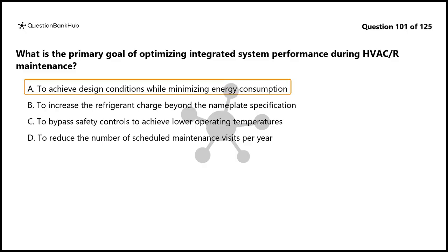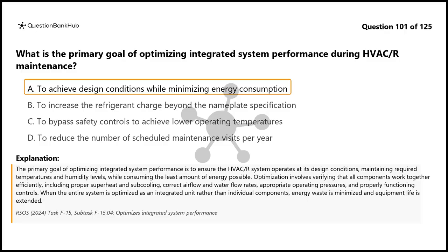The correct answer is A. The primary goal of optimizing integrated system performance is to ensure the HVAC/R system operates at its design conditions, maintaining required temperatures and humidity levels, while consuming the least amount of energy possible. Optimization involves verifying that all components work together efficiently, including proper superheat and subcooling, correct airflow and water flow rates, appropriate operating pressures, and properly functioning controls. When the entire system is optimized as an integrated unit rather than individual components, energy waste is minimized and equipment life is extended.